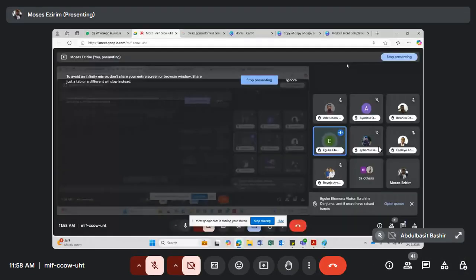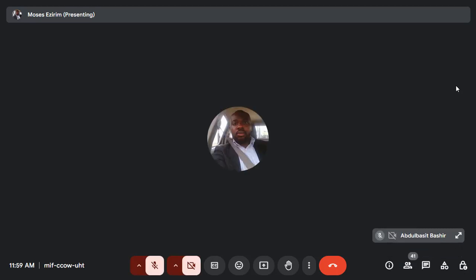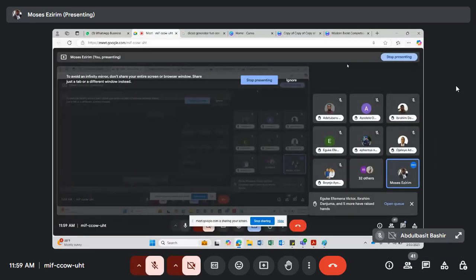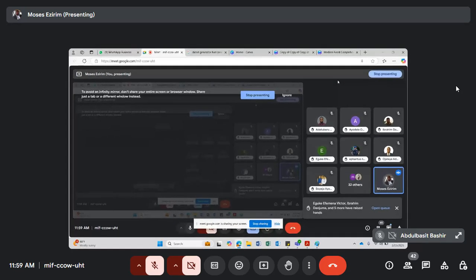I want to ask a question, and from your explanation, if the cable inside my... it means if one of the inverter is overloaded, of course, it will be hot because that's the transmission. Obviously, the cable will be hot. That's the reason why, when you do your design, you do your audit. You are going to see if you need to do load balance, so the load on line 1 will not be high. The ones is even tripping on high temperature. So I need to go and rebalance that.